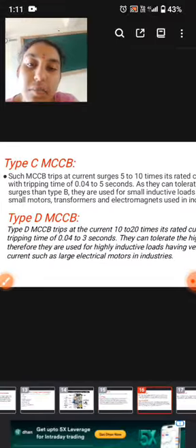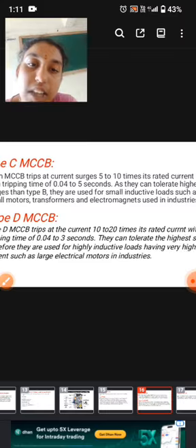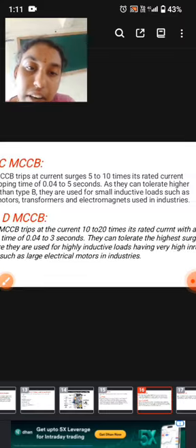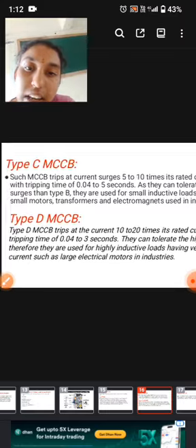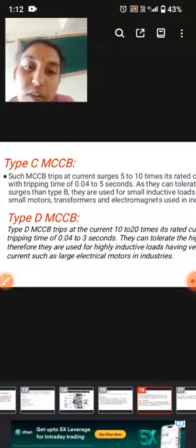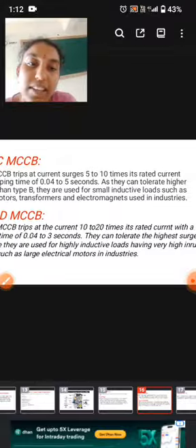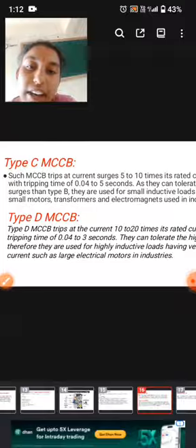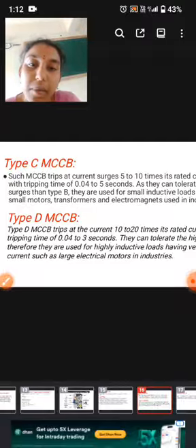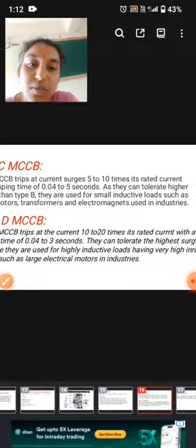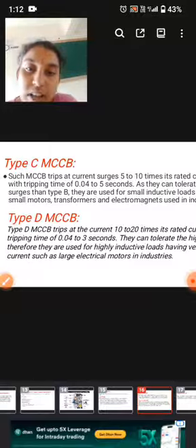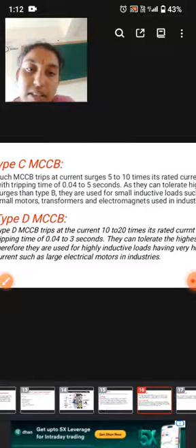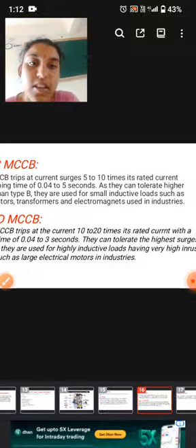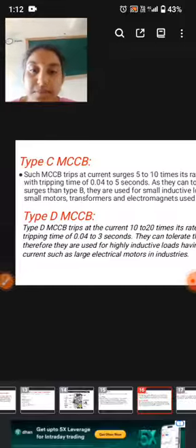Type C MCCB. Such MCCBs trip at current surges of 5 to 10 times their rated current, with a tripping time of 0.04 to 5 seconds. As they can tolerate higher surges than type B, they are used for small inductive loads such as small motors, transformers and electromagnets used in industries.